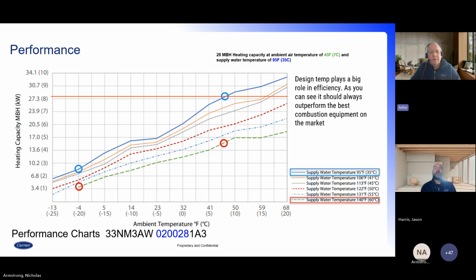Hydronically, 95-degree Fahrenheit water is very low. And this would represent a type of hydronic system such as floor warming, something with large mass. The rule of thumb is higher the mass, lower the temperature. So floor heating, floor warming has a very large mass. And because of the large mass, we can satisfactorily heat a building with a very low temperature. When you get into low mass, now we've got to drive higher temperatures to get the same equivalent output.